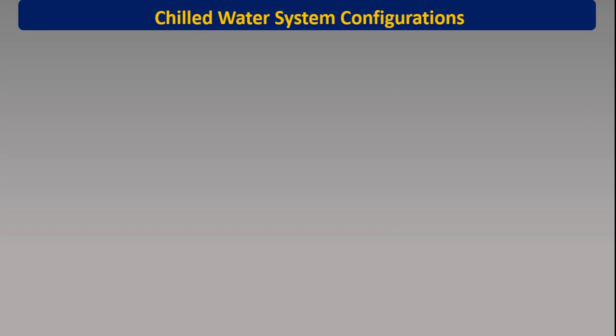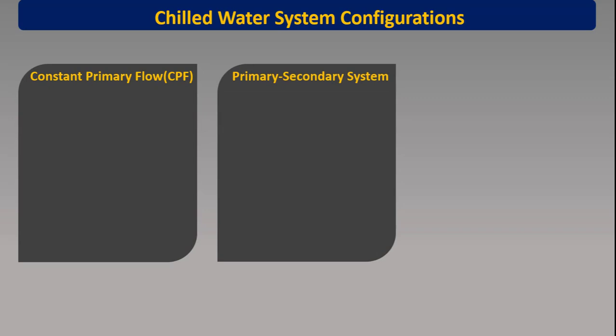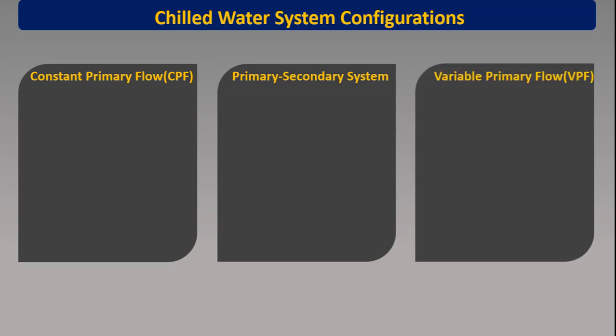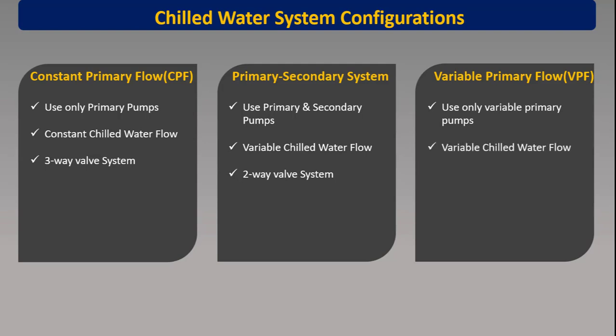Now let's have a look at different chilled water system configurations. First, we have a constant primary flow chilled water system. Then we have a primary-secondary system. And finally, we have a variable primary flow chilled water system. In a constant flow primary chilled water system, we use only primary pumps and water flow is always constant — this is a three-way valve system. The primary-secondary system uses both primary and secondary pumps and is a variable chilled water flow system using two-way valves. The variable primary flow system also uses only variable speed primary pumps and two-way valves.